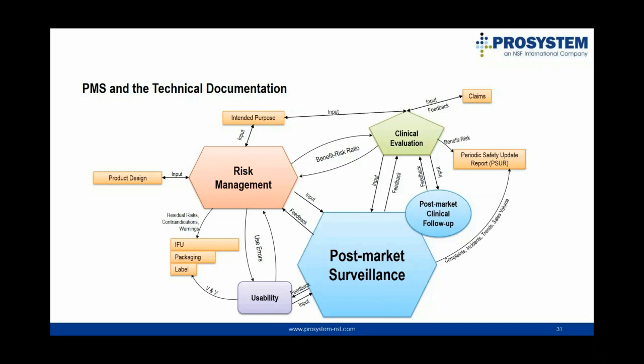So what is the payoff out of this additional regulatory burden? Well, obviously making sure to meet regulatory requirements, but more importantly, post-market surveillance is one of the activities that can signal a change in medical device performance or a potential safety issue with the medical device after market release. Post-market surveillance can also identify that the organization's defined lifetime of the medical device has changed, or that the medical device is not current state of the art due to competing medical devices, the evolution to the state of the art, or alternative medical treatment procedures. These signals can trigger a design modification, a change in intended use or purpose, a new medical device design, or even the removal of medical devices from the market.